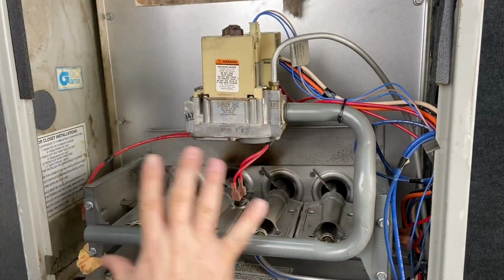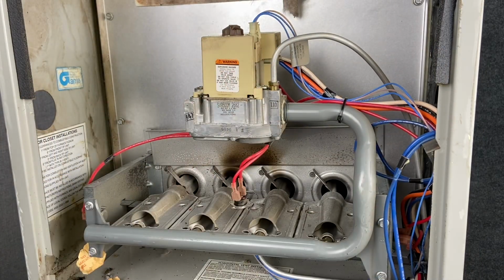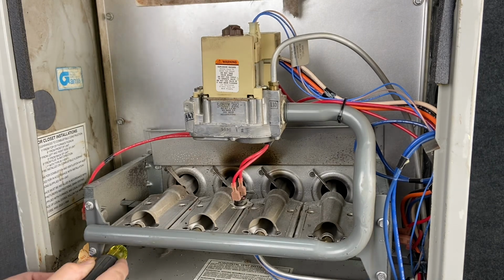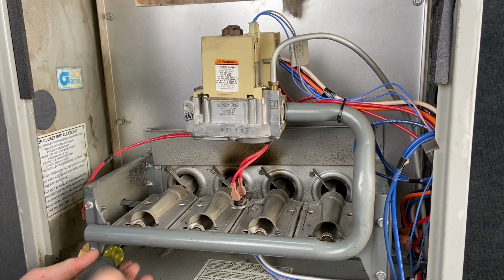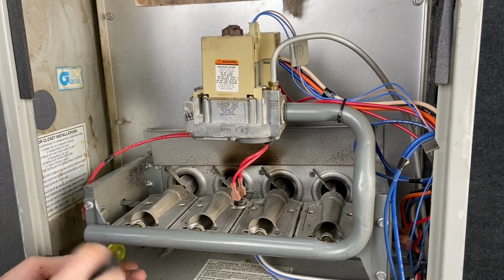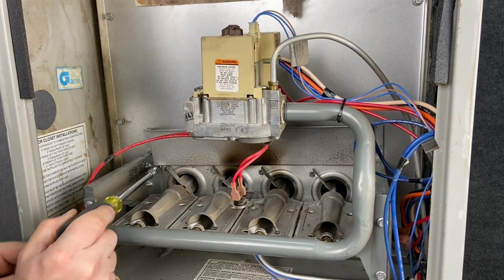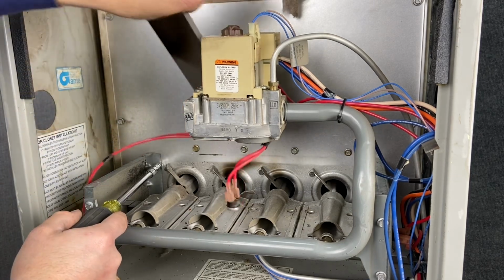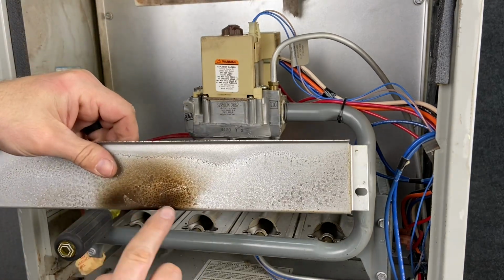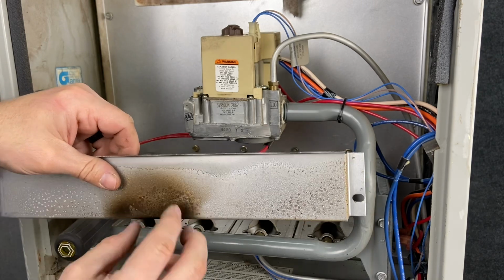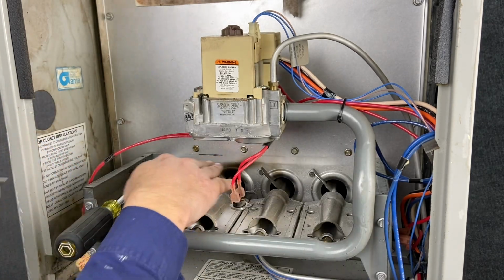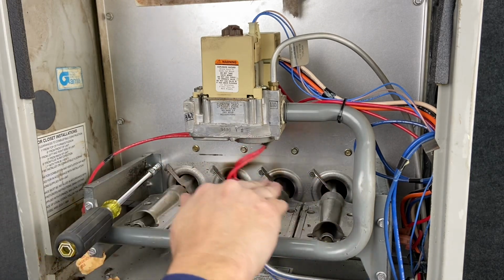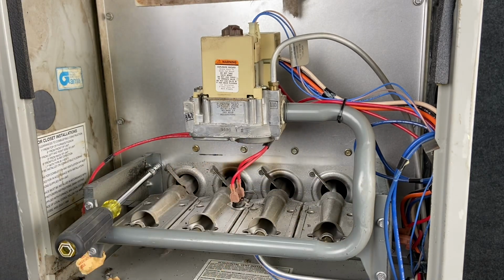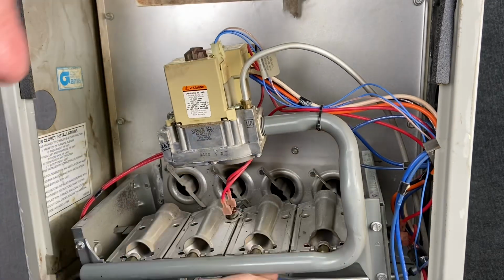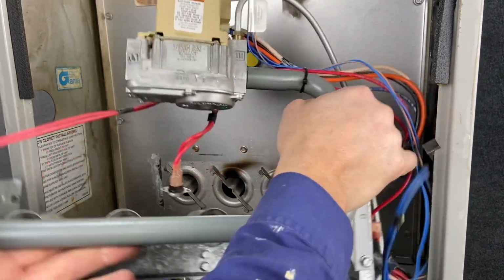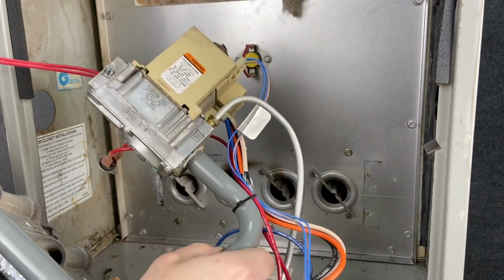Next, I'm going to try to take this assembly out as one piece so we can look at it, and then we can take it apart individually. There should be 4 screws holding this on. We'll see if that's correct. If you notice this burnt spot here, this is where the pilot light has been burning up against this shield. This shield goes against the back. I've already taken the shield off across the top that protects the burners so that we could get the video. Now we can get this almost as one full set.